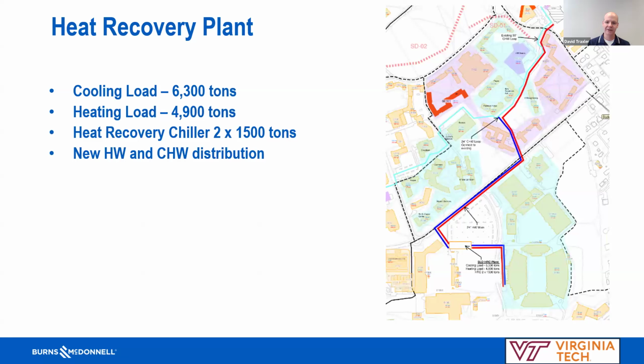Now, the final area I'm going to talk about is the athletic and student life district. This consists mainly of the stadiums and athletic facilities. There are some offices in this area of campus and some lecture buildings. But there are a lot of student housing and dining facilities. So here, two 1,500-ton heat recovery chillers, similar to the other central plant. And here we had new hot water and chilled water distribution. The chilled water just needs to connect into the existing distribution, and this would be all new hot water distribution, since there is no hot water distribution on campus right now. And the loads are 6,300 tons for cooling and 4,900 tons for heating.